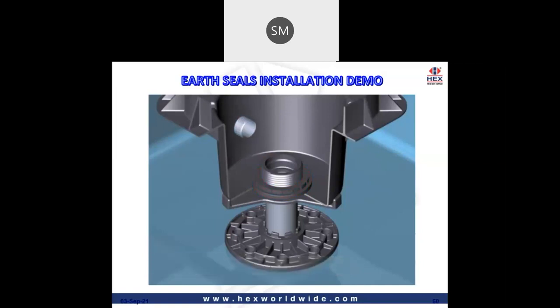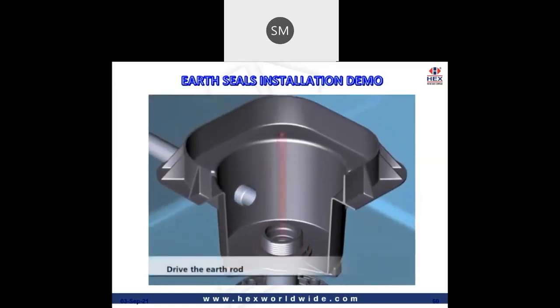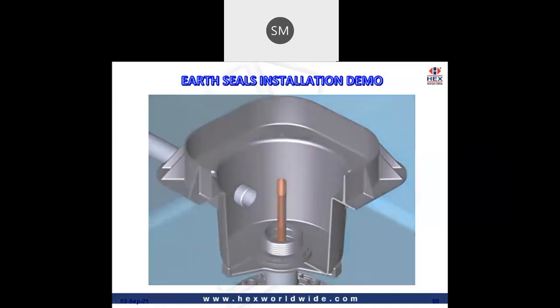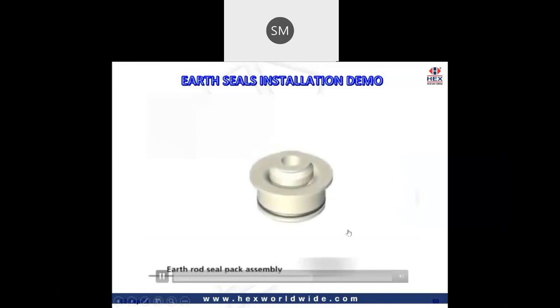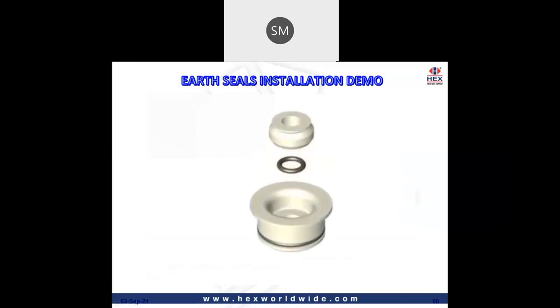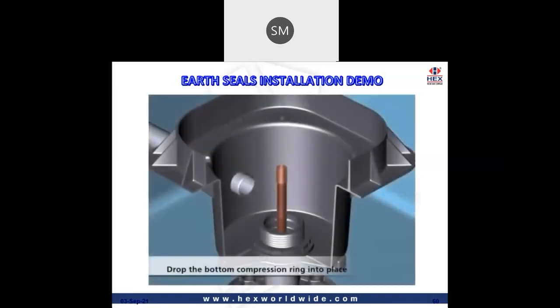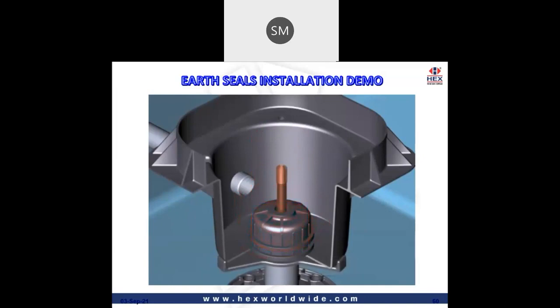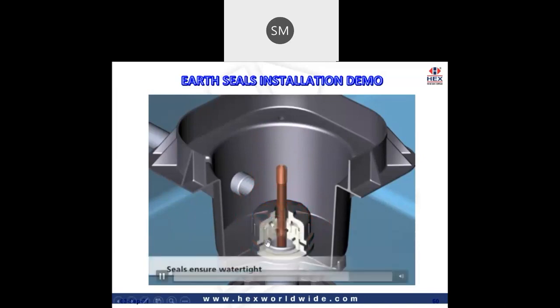You can then just pass on the pipe through which the conductor will be coming, which will be connected to the earth rod. The earth rod is then driven through the earth pit and into the bottom seal, into the ground. And the seal pack is opened up and it is placed into the slot that has been designed for the seals. Now these seals effectively will seal the earth rod and will not allow any water to come into the earth pit chamber. This is then tightened into place. Once this is done, you can see the seals are all in place here.